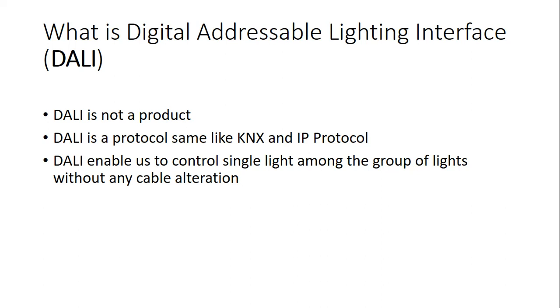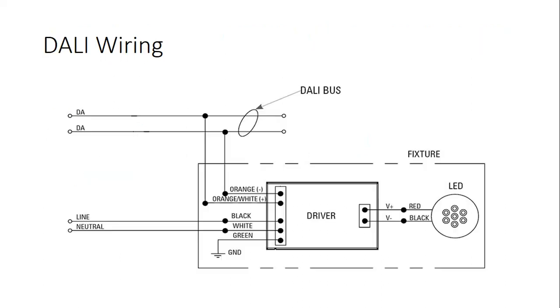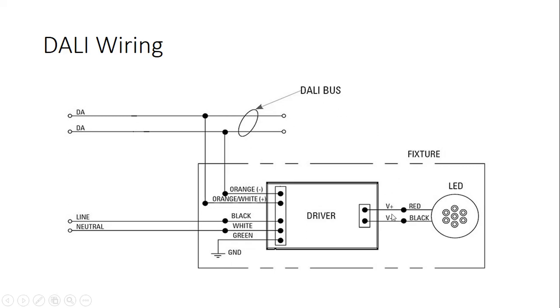So this is how DALI wiring is. This is DALI bus, and it keeps going on. At this point we have one DALI LED connected here, they call it fixture. Then there will be another one somewhere, and another one somewhere, and the maximum we can connect up to 64 on this one line. Each fixture will need DALI in, DALI plus and minus, direction doesn't matter.